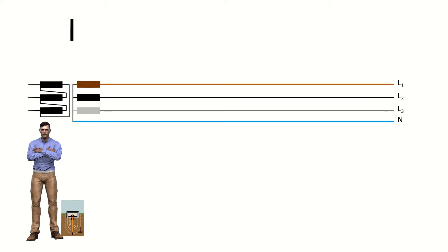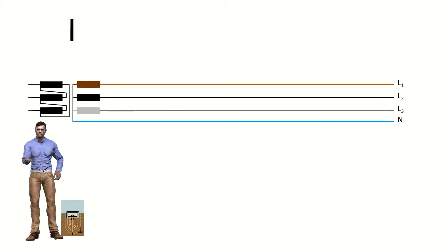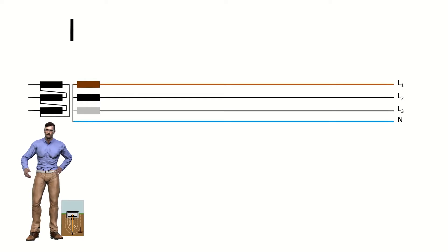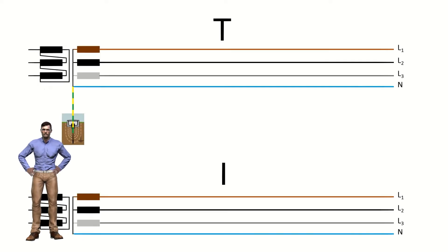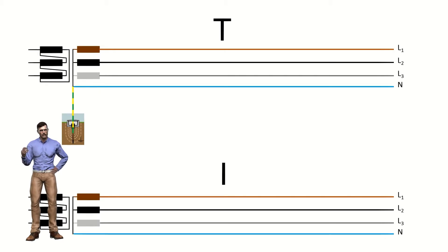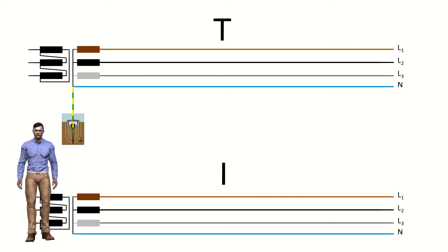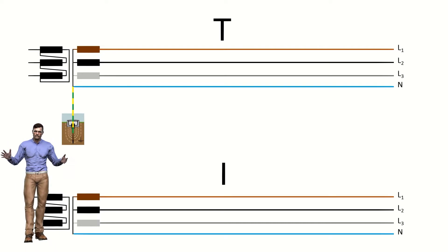We use the letter I if the active parts of the installation are isolated from ground, or if there is a connection point through a high impedance. Therefore: T if the power supply is grounded directly, and on the other hand I if it is connected with an impedance or isolated, that is, an infinite impedance. With this word game you can easily remember it.